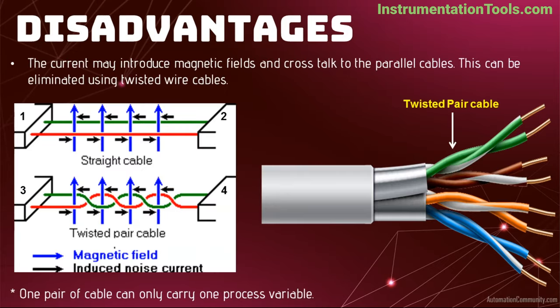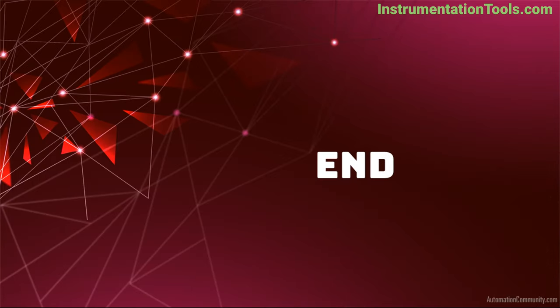There are two disadvantages. First, current signals may induce small magnetic fields in straight wires, which may affect the signals. To avoid this, twisted pair cables are used. The magnetic fields induced in the two cables cancel each other out, resolving the magnetic field problem. Second, each pair of cables carries only one process variable.